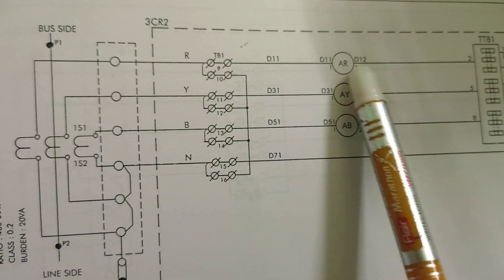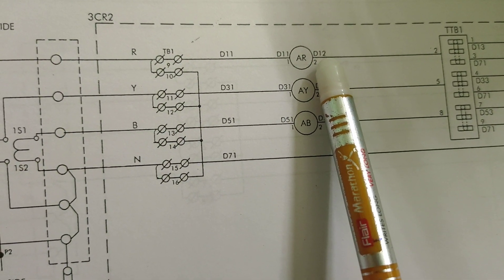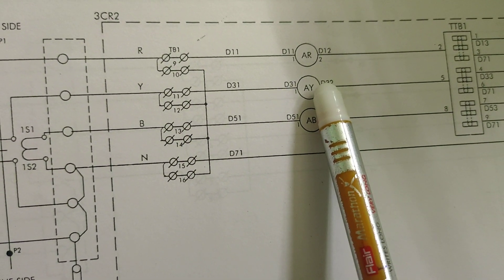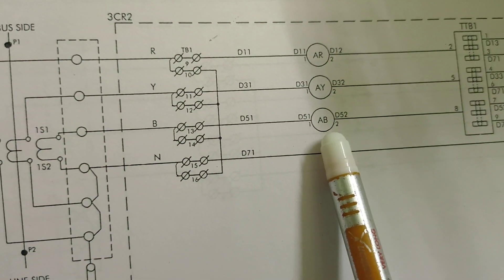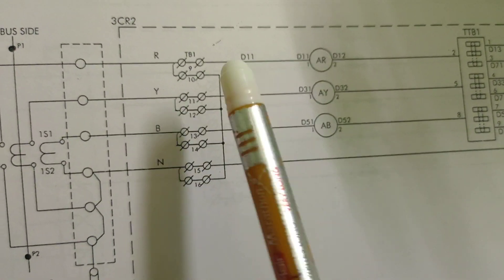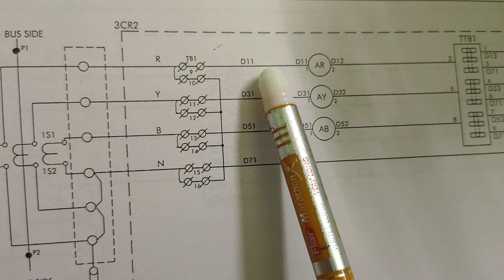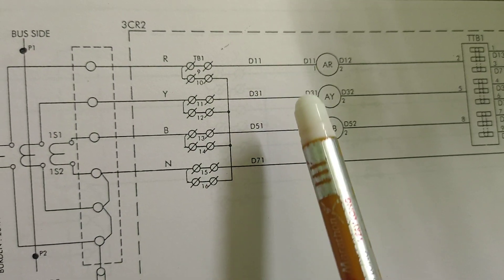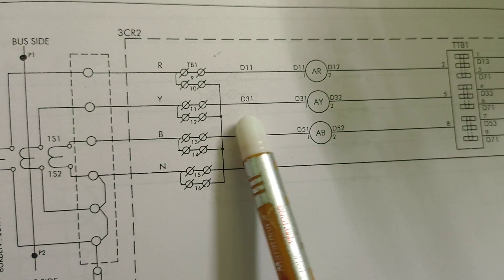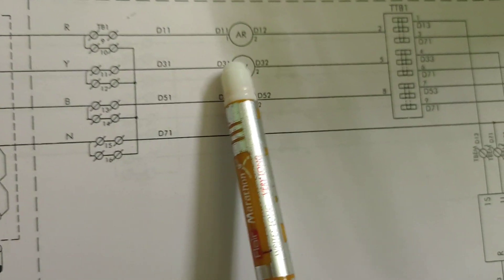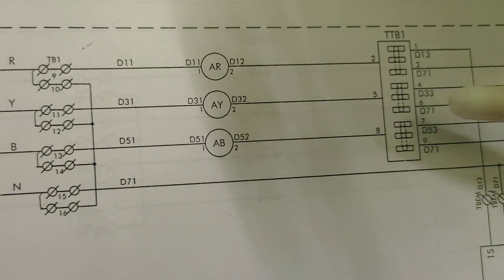From the TB, it goes through the ammeter. AR denotes the red phase ammeter, AY denotes the Y phase ammeter, and AB denotes the B phase ammeter. For core 1 metering use, the ferrule numbers used are D11, D31, D51, and D71. These go to the TTB — the test terminal block.